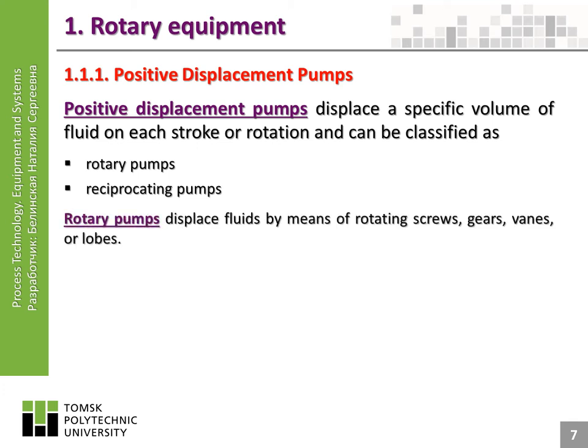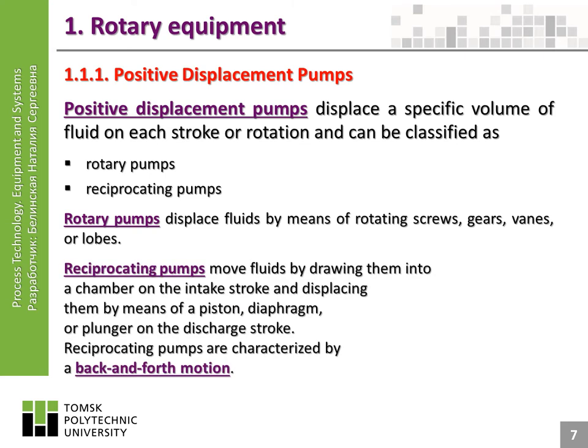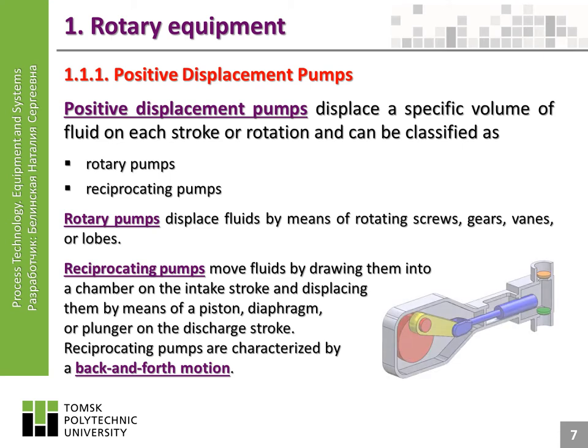Rotary pumps displace fluids by means of rotating screws, gears, vanes, or lobes. Reciprocating pumps move fluids by drawing them into a chamber on the intake stroke and displacing them by means of a piston, diaphragm, or plunger on the discharge stroke. Reciprocating pumps are characterized by a back-and-forth motion.